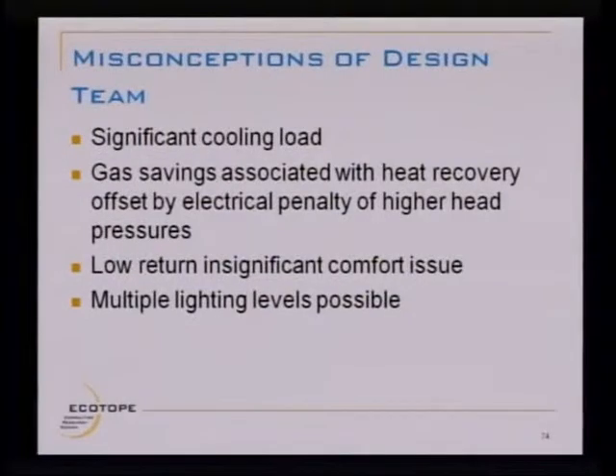And it was remarkable how long it took for me to hammer through their heads that, yes, you're right, the refrigeration system's going to use more energy, but the gas savings is huge. So it's just bridging across those two different disciplines is difficult. The importance of low return air was missed by everyone on the project, primarily thinking that it was only a comfort issue and that comfort issue wasn't that big. Not understanding the point that I was making earlier, that you have to have cool air running over the coils to be able to carry that heat back into the space.